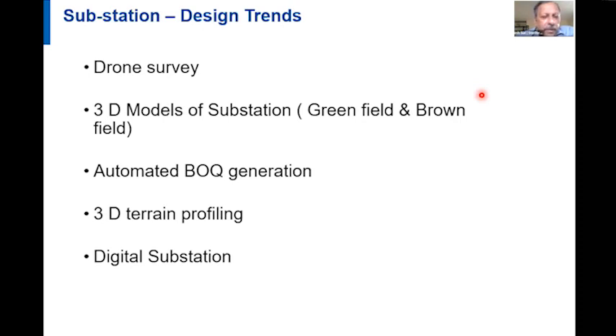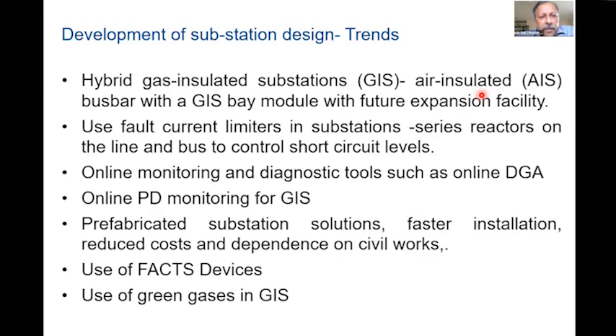And of course, digital substations, which have already been mentioned. Other trends in substation design, as I mentioned, include hybrid gas-insulated and air-insulated substations. Short circuit current is a problem, so today fault current limiters are available which can be put in substations, removing the need for splitting buses. Series reactors can also be placed on the lines or buses to control short circuit levels.